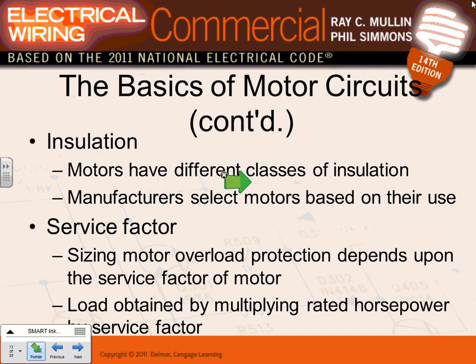Motors have different classes of insulation. For motors, guys, they have classes of insulation. Higher class means higher temperature rating. We have A105 to H180. These insulations, Darren, are the windings, the magnetic winding insulation inside the guts of a motor. If it's rated for higher temperature, it means you can abuse the motor a little bit more, and it wouldn't smoke on you.